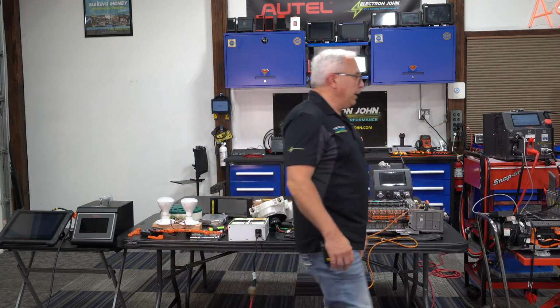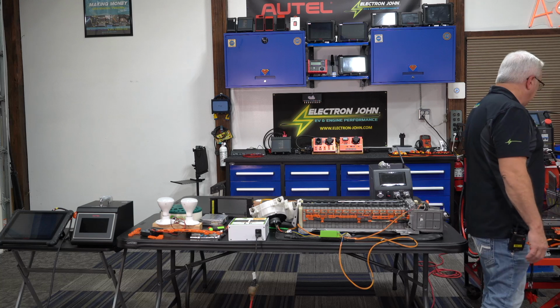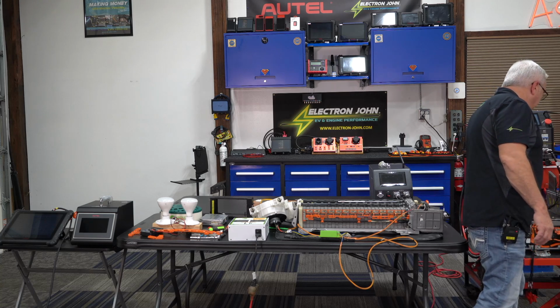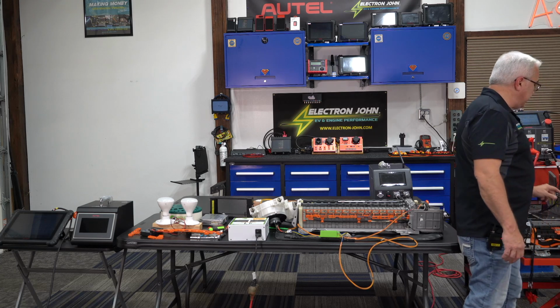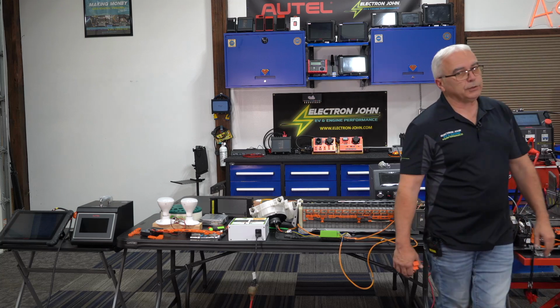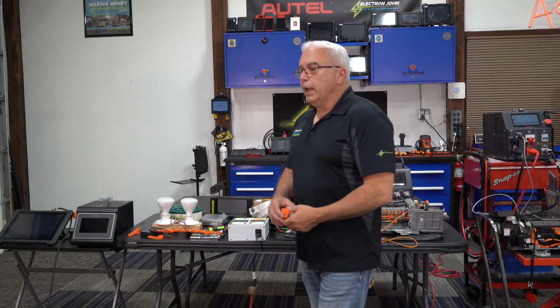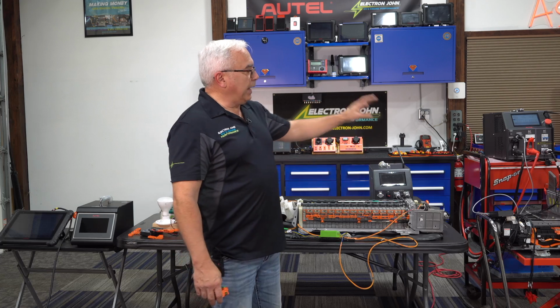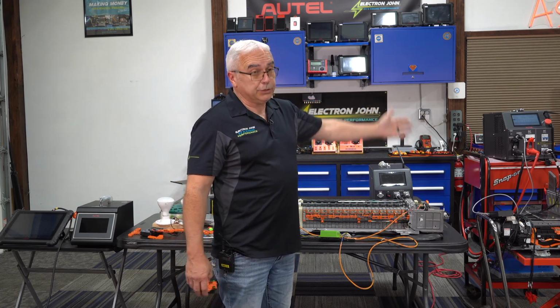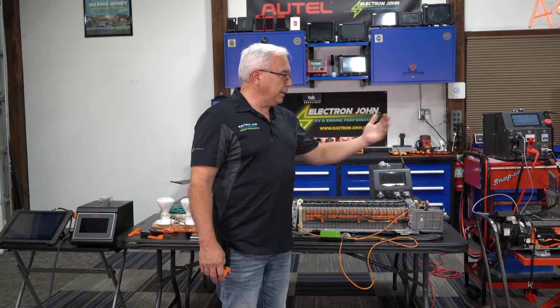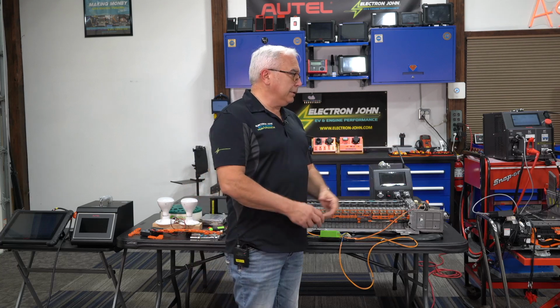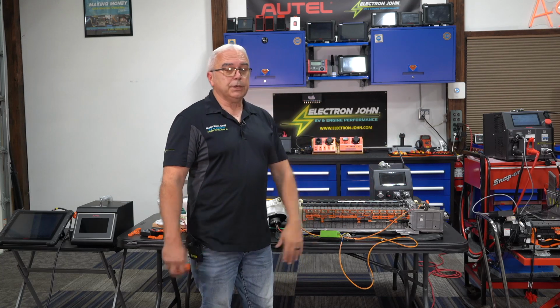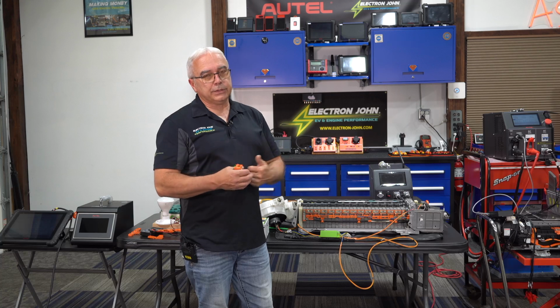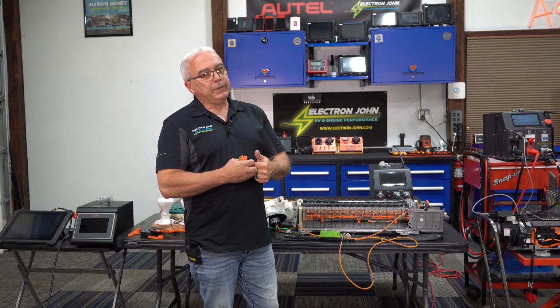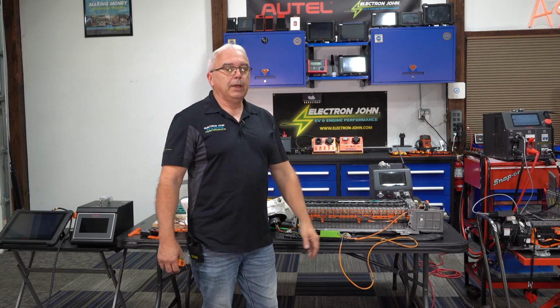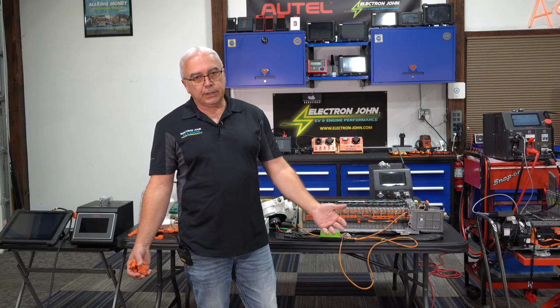So at this point, once I had everything hooked up the way I thought it should be, I'd have to hook up these last two wires, the two big heavy duty wires, to the positive and negative of this module. Then I would hit the start button. That start button will allow me to start, since we selected discharge, to discharge that particular battery module. Now inside that module there's 8 cells, so it's discharging all 8 of those cells simultaneously. And again, depending on how I program the setup is going to dictate how fast they're going to discharge.